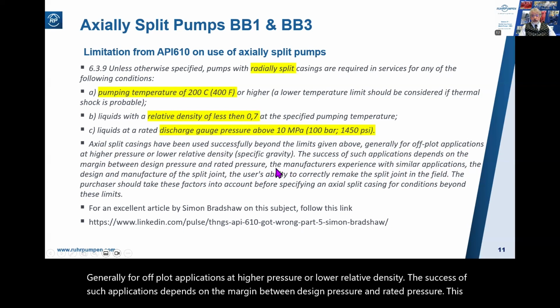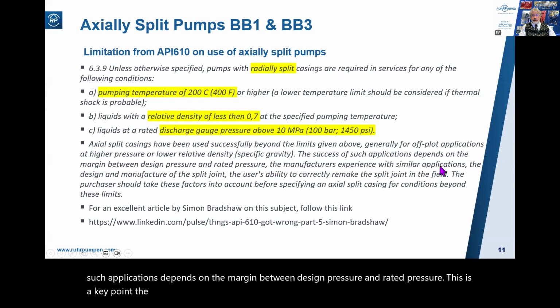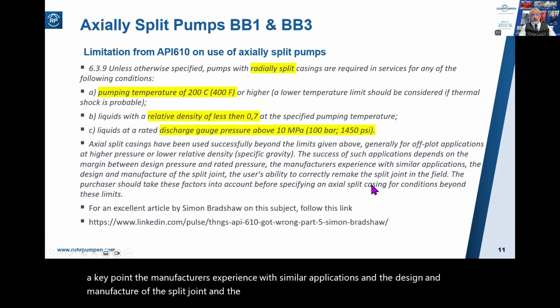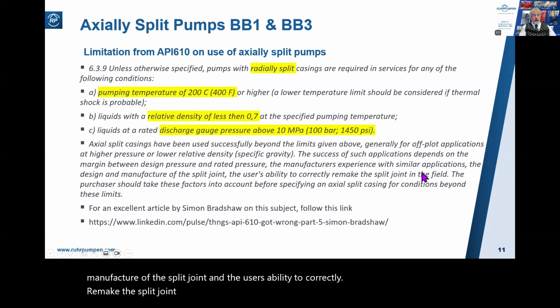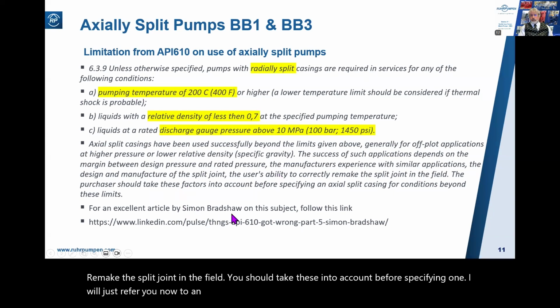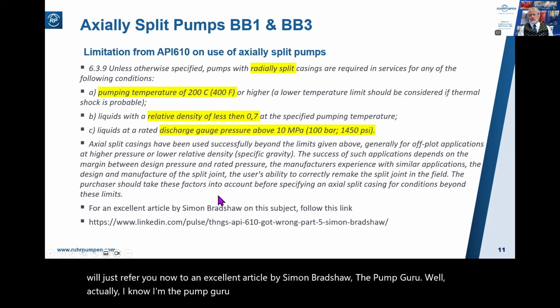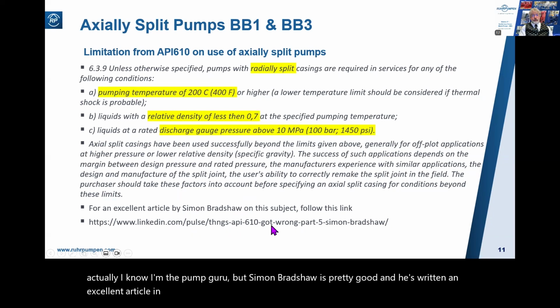The success of such applications depends on the margin between design pressure and rated pressure. This is a key point. It also depends on the manufacturer's experience with similar applications, the design and manufacture of the split joint, and the user's ability to correctly remake the split joint in the field. You should take these into account before specifying one. I will just refer you now to an excellent article by Simon Bradshaw, the pump guru. Well, actually, I know I'm the pump guru, but Simon Bradshaw's pretty good. And he's written an excellent article in his series of things that API 610 got wrong on this particular subject. So follow that link later on.